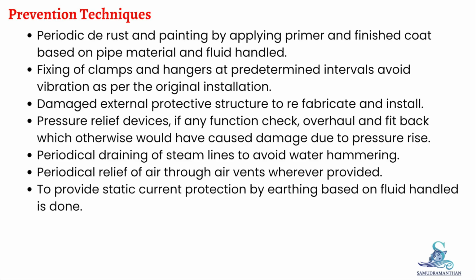Pressure relief devices, where fitted, must be periodically checked, overhauled, and refitted, as failure of these devices can lead to damage due to pressure rise. Steam lines must be regularly drained to prevent water hammer, and air must be periodically released through air vents wherever provided. Static current protection through proper earthing, based on the fluid handled, is also essential.